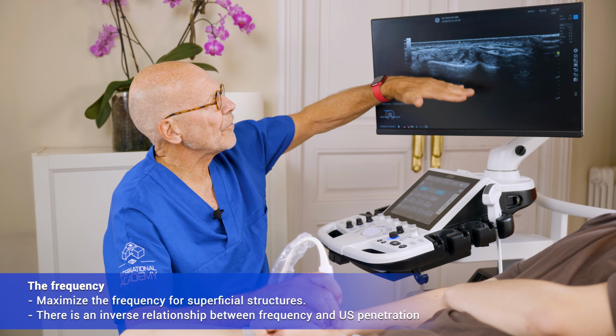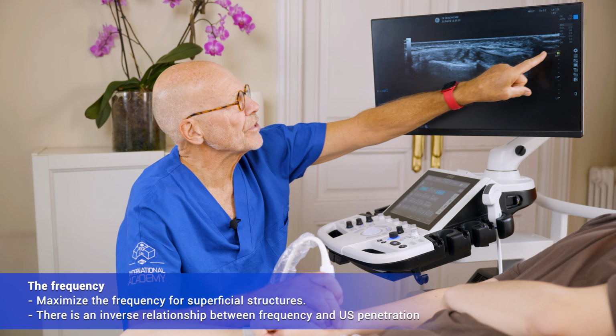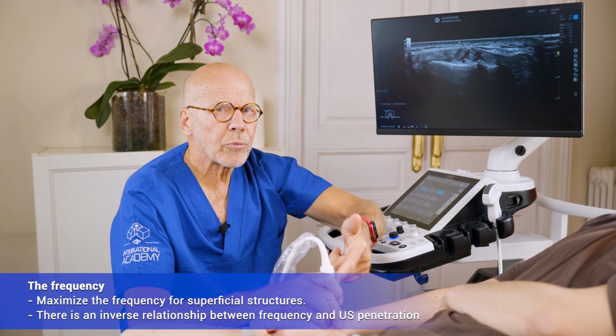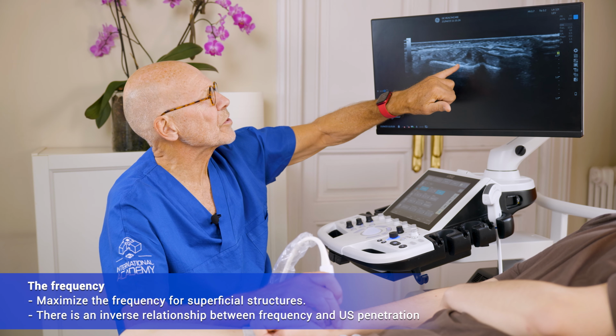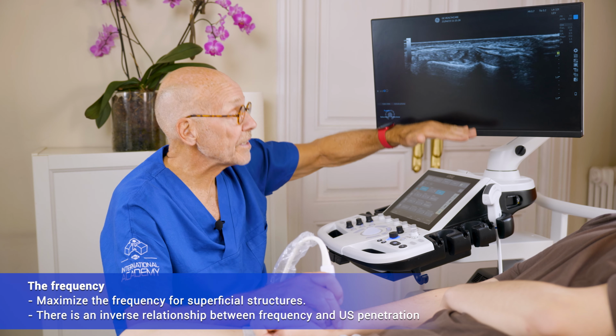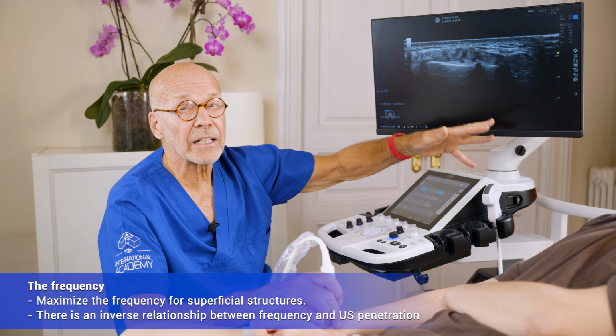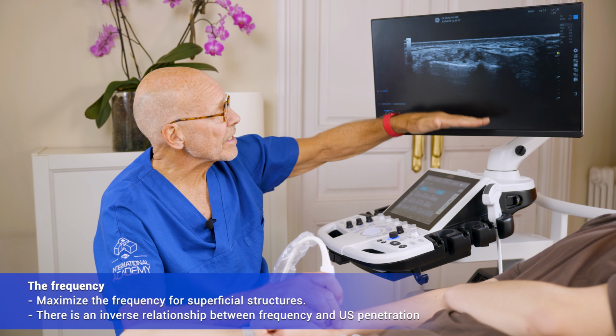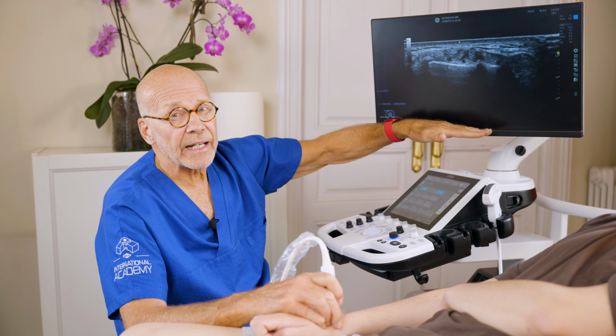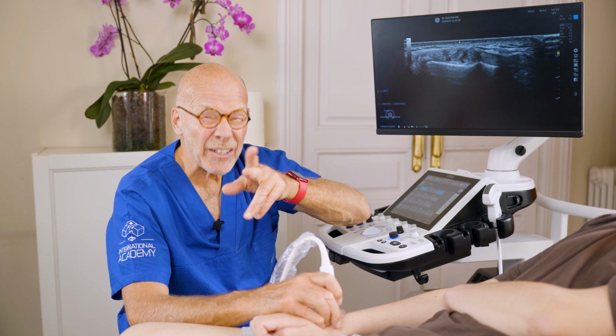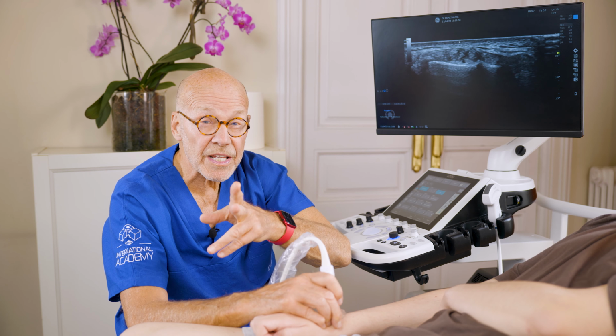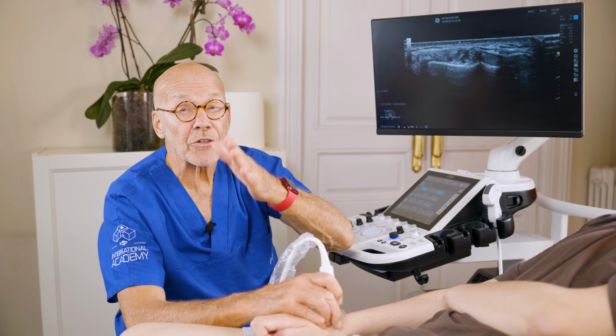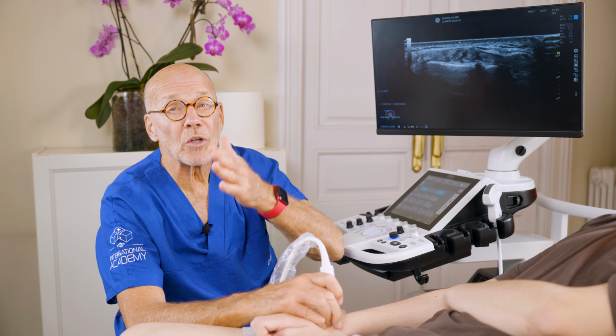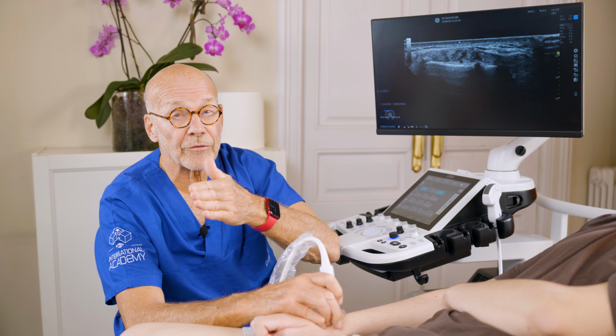So now we have a very superficial structure. We're using our maximum frequency that this probe allows, and it'll give us the best resolution possible. Now, if this were a deeper structure, we'd clearly want to lower the frequency so that we could see a structure much deeper. So it allows this penetration. Remember that inverse relationship between frequency and penetration. So the more you have to penetrate, the lower the frequency. You need to lower that frequency.